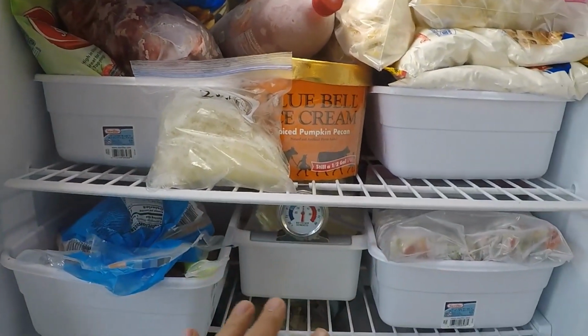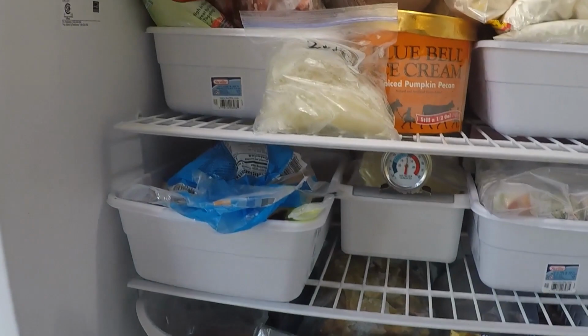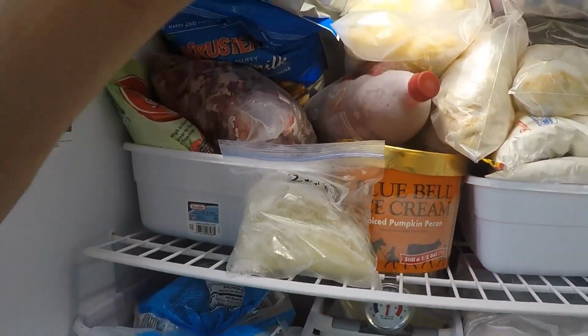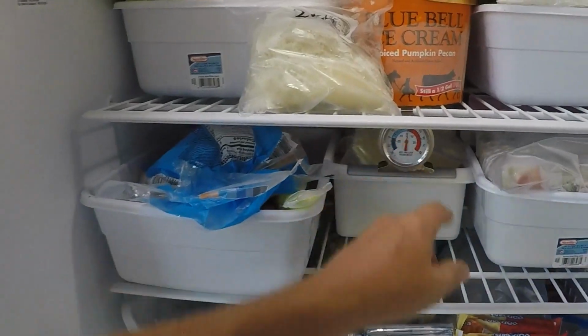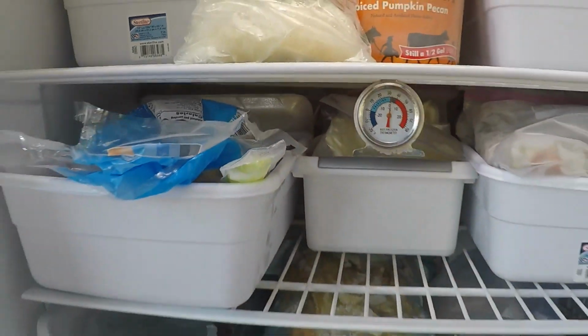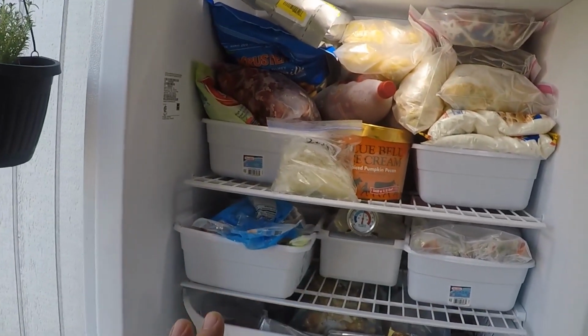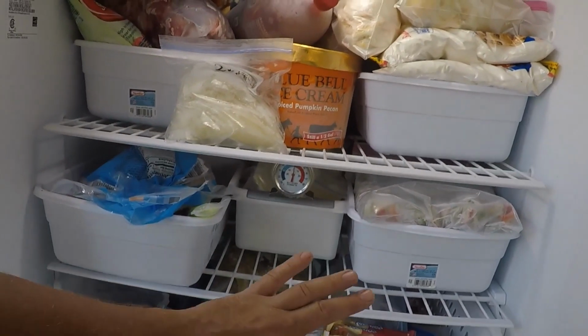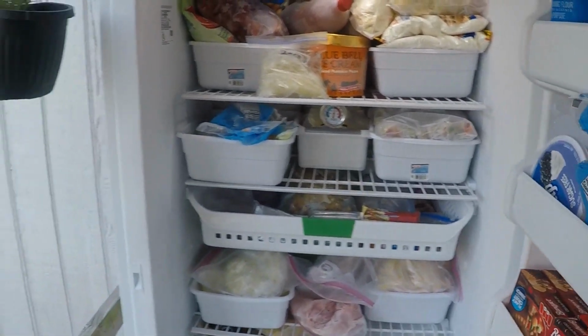If it doesn't defrost, there's no circulation of air. It also has a little fan. That little fan can go out, and you're no longer circulating air in your box, and you'll begin to see your temperature warm up. Now, I've had this open, and it's up to 30 degrees right now. Stuff's not thawing because as soon as I close the door, because this thing's full, it'll cool right back down. It's running right now, won't be no big problem.